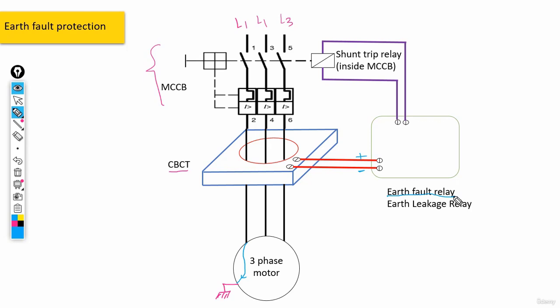And now, through the outgoing current of this earth fault relay, the shunt trip set inside our MCCB breaker would be activated. In other words, the breaker that was actually on so far would immediately be set on trip. And well, as a result of this, the electrical current would be cut off and our three-phase motor would stop working. It would be turned off. Right, guys, so basically, this is how you can protect your three-phase motor through using equipment such as MCCB breaker, CBCT transformer, earth fault relay, and also shunt trip relay.